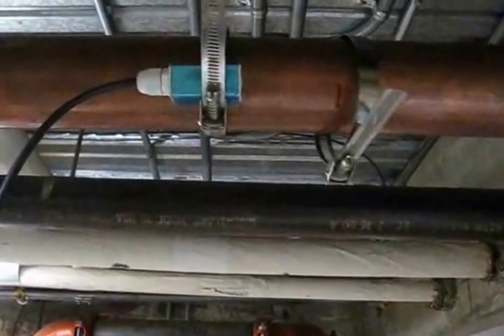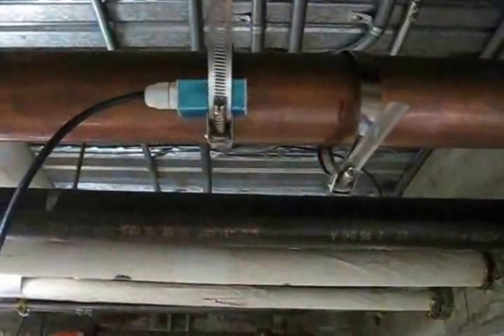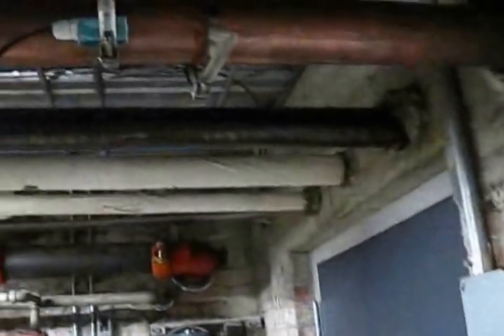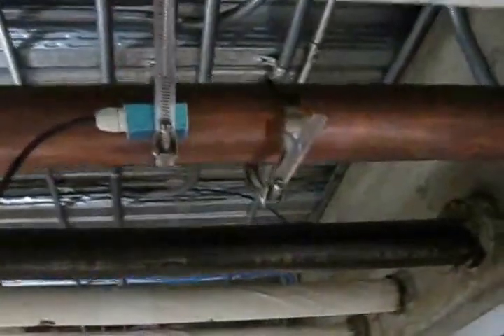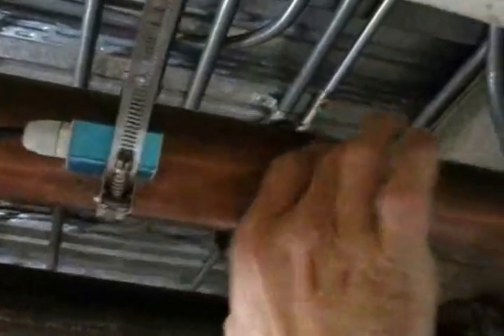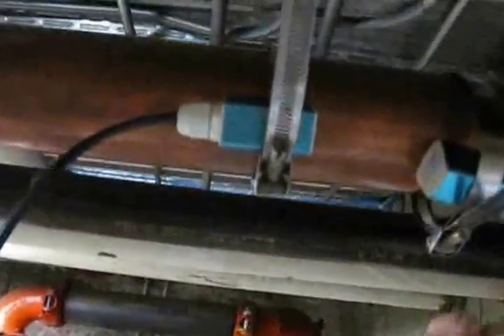Now that we've installed the first transducer and its location is on the side of the pipe, we will add couplant to the second transducer, applying it in the same manner as the first. We have our pipe location already marked. We take the transducer and we slide it in. Again, the wires are out, and face to face we have our 2.95. At this point, I'll tighten this clamp.